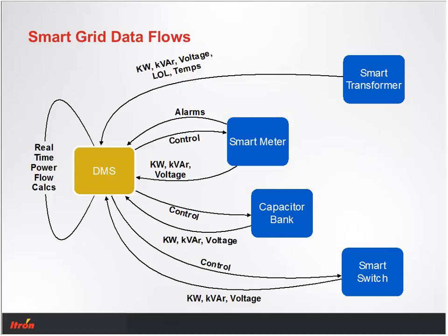We have smart switches placed for our auto restoration scheme, and those involve control as well as those same voltage measures. We have load at numerous places on the primary, and if you aggregate all the loads in between, they should add up. So we can add all the meters in between, and they should add up to the aggregated points, which are the cap banks or the smart switches. That gives us a nice double check to understand that our data is valid.